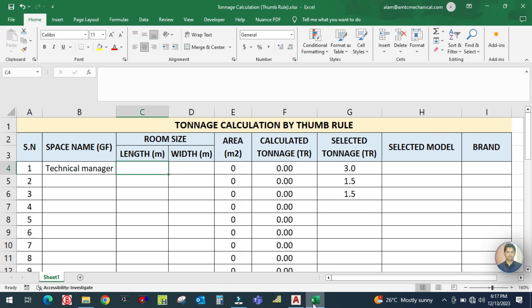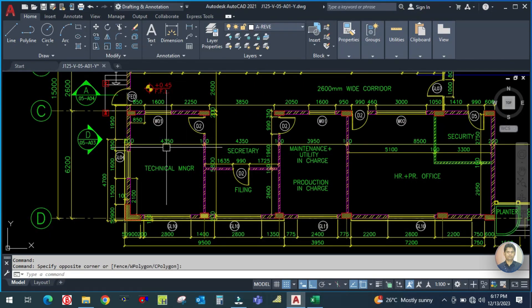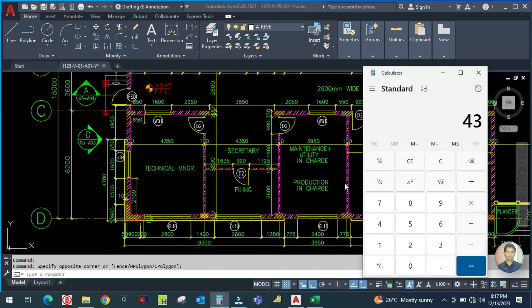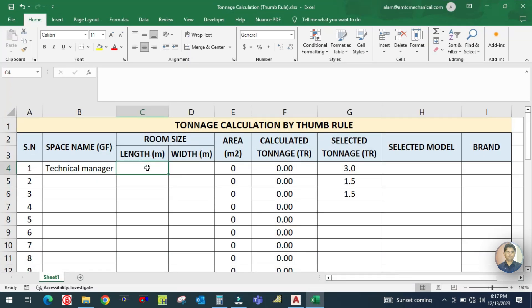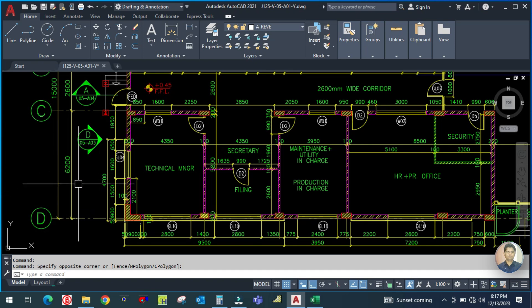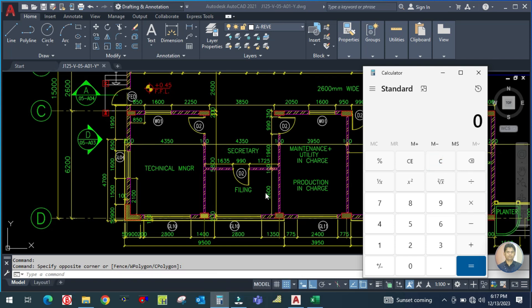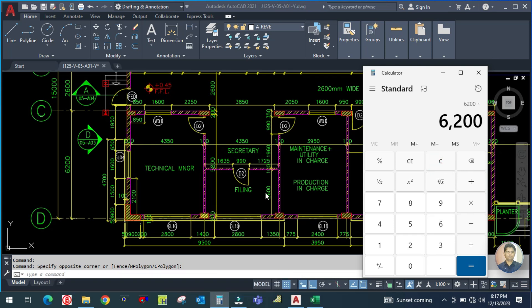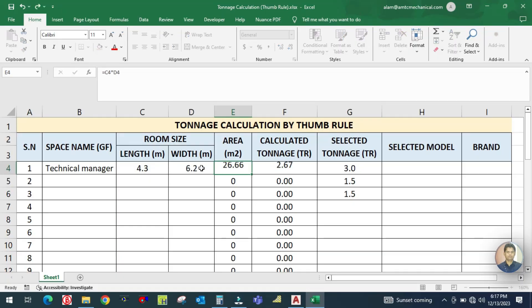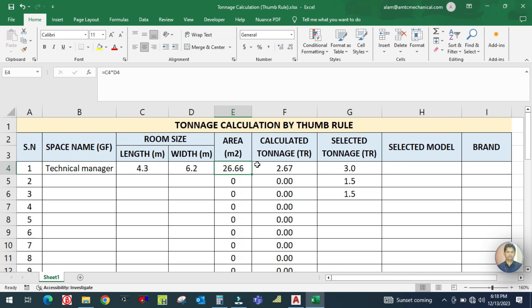The dimensions on the drawing are given in millimeters, so you need to convert to meters. For example, the width is 4350 mm divided by 1000 equals 4.3 meters, and the length is 6200 mm divided by 1000 equals 6.2 meters. Once you enter the length and width, the area is automatically calculated, and then divided by 10 — because for the thumb rule we use 10 square meters per ton.